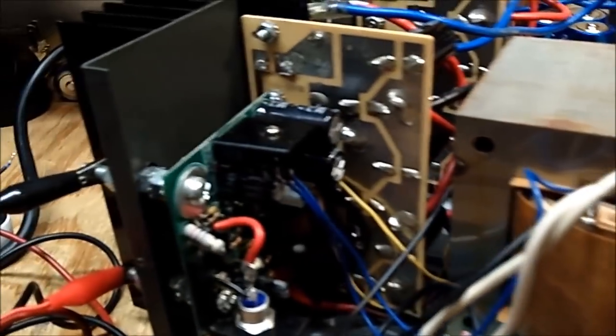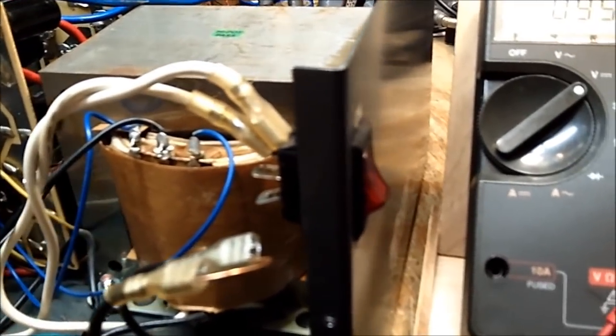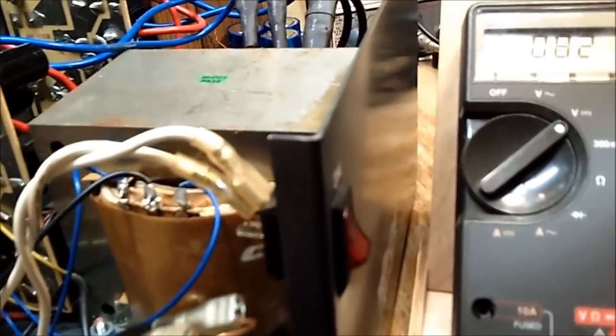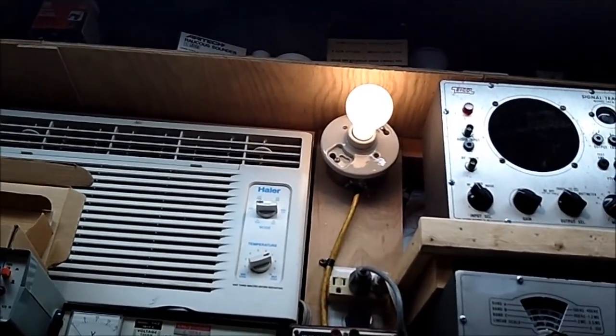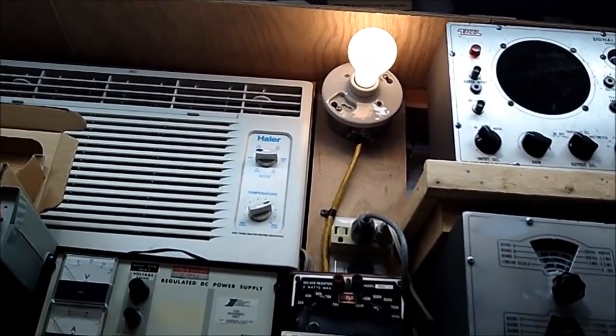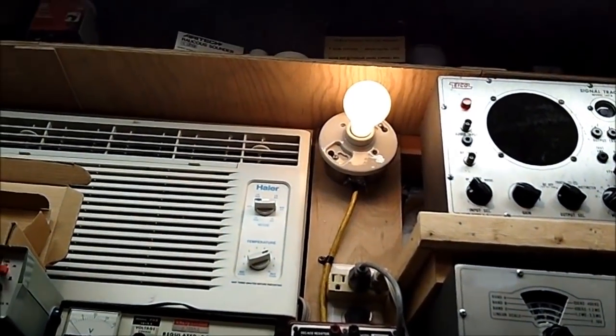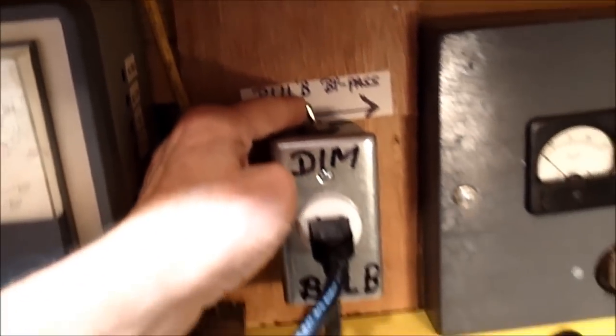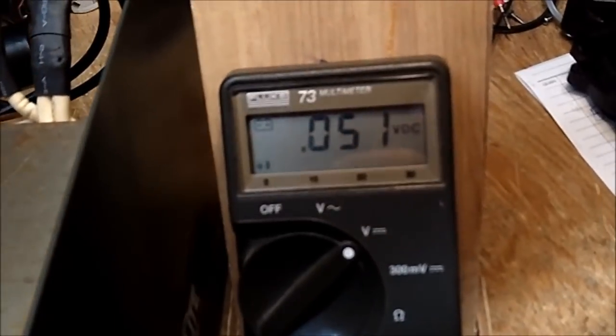That would mean that the power transformer is good, and that the switch was defective. Now we still got, turned the bypass off, so we're running through the dim bulb, so we obviously still got connection right here, so we didn't lose connection. Now let me throw that bypass over again and watch the meter.